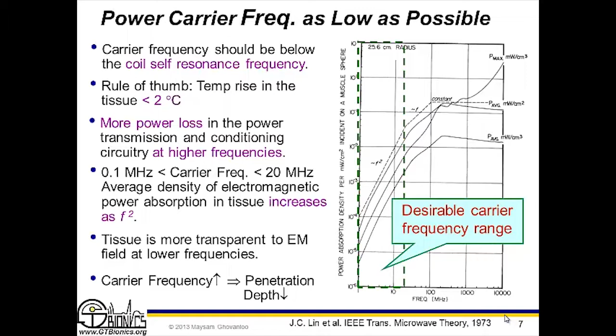But that primary coil has internal resistance, so when you drive it, you dissipate some power. There is also power dissipation in the tissue, which is that curve I showed. Thanks to the proper choice of frequency—low power frequency, which all cochlear implant manufacturers like Advanced Bionics and MED-EL in Europe use, somewhere between 2 to 40 or 50 megahertz—the tissue loss is almost negligible, relatively speaking. Then there is secondary coil loss, because that coil isn't ideal either; it has parasitic resistance, so there's power loss there too.